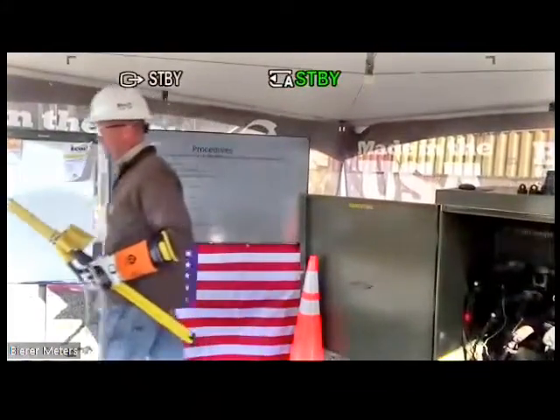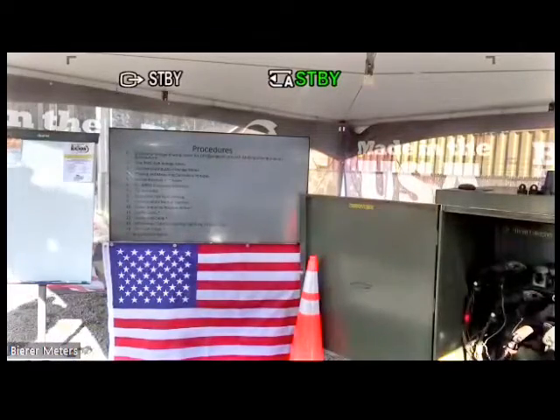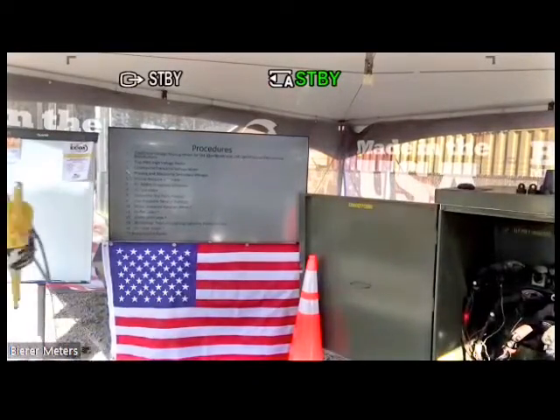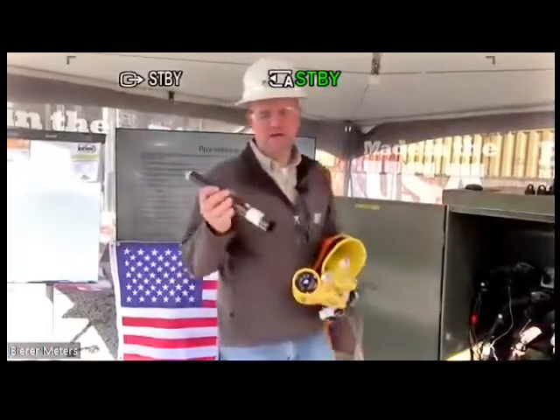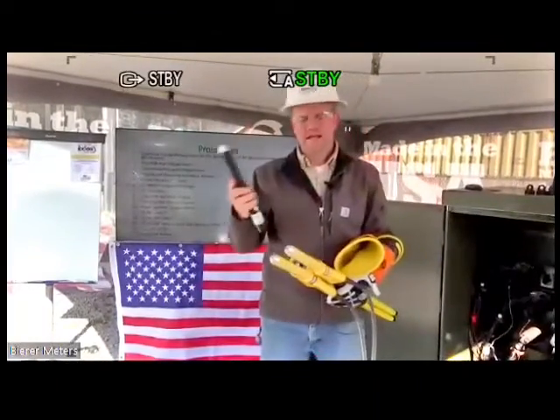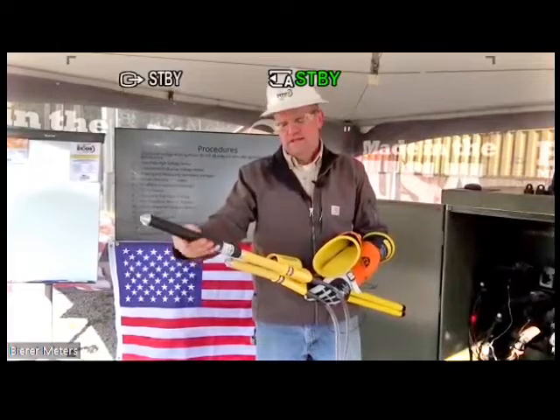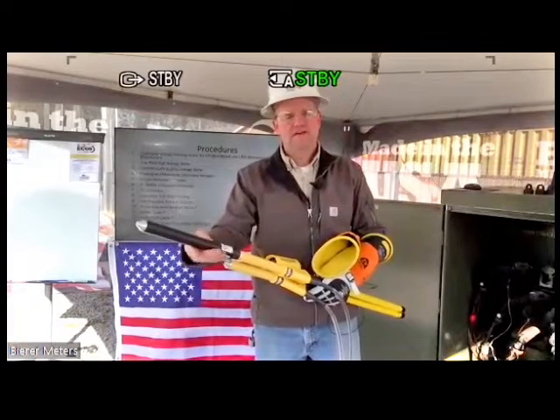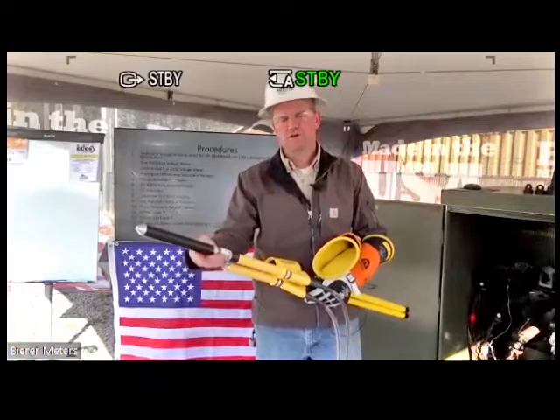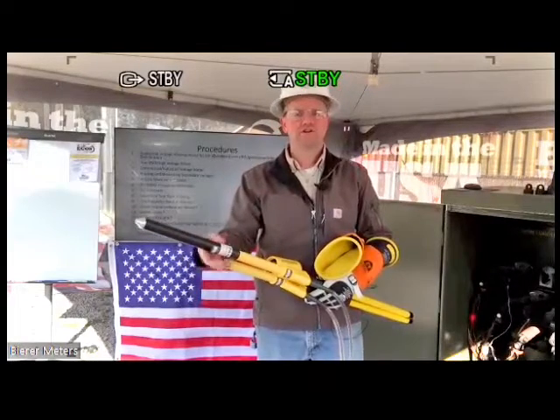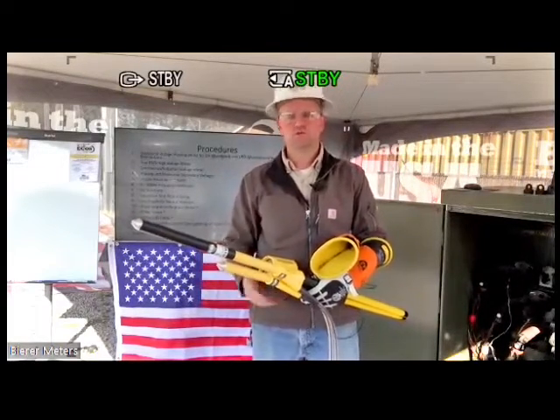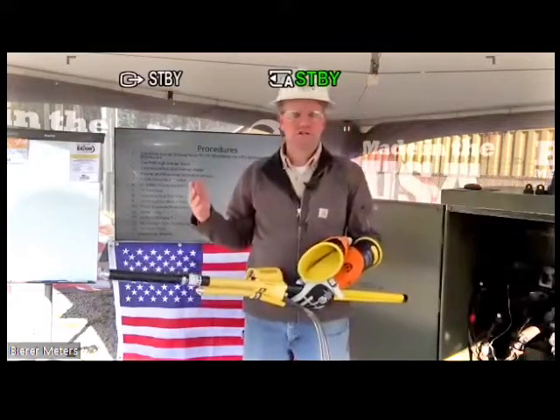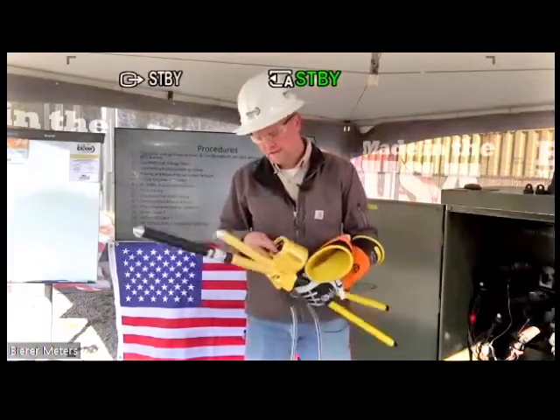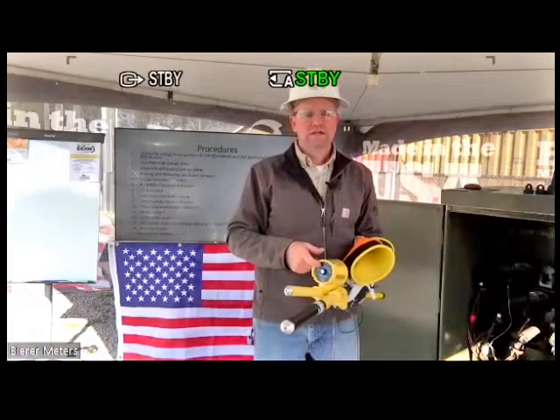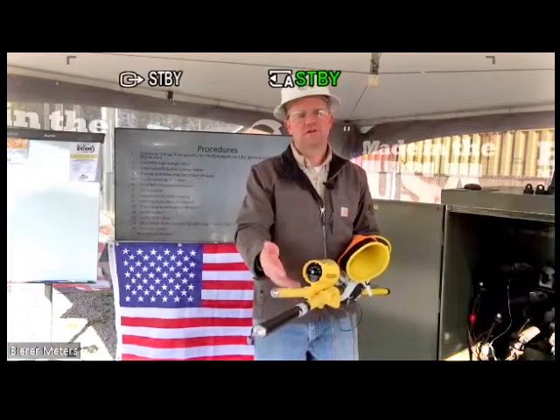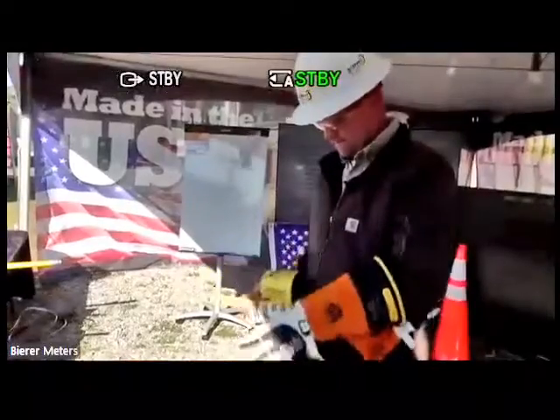The next one is DC voltmeter. And again, I can use my DC adapter, my 100-volt adapter. When we were ringing out the line earlier, and this would be no different from checking batteries in a substation, if you want to use your truck battery as your known voltage source before you use the tool, you can do that. So you should see your 13 or 14 volts, whatever the truck battery is. I want to leave the tool in the 2 kV switch position since this is only 100 volts.